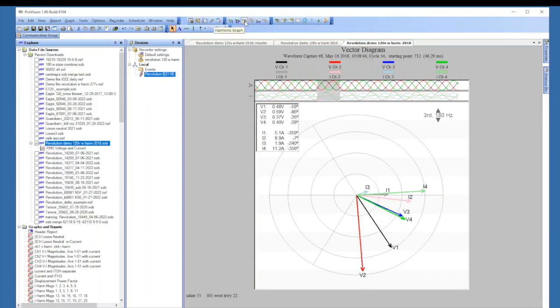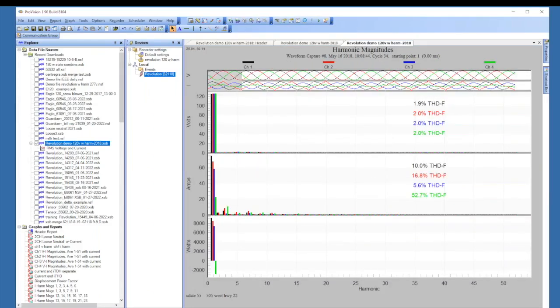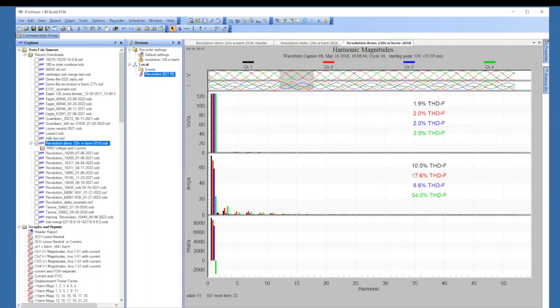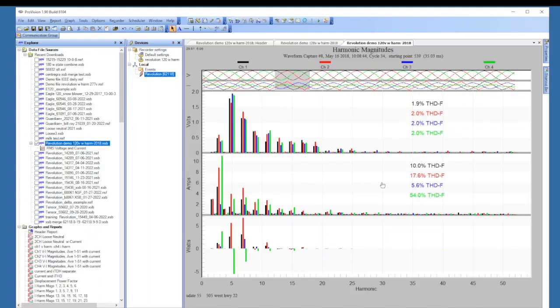If we go and click on the H for the harmonic, we get harmonics, and we can see that we have total harmonic distortion there. So again, we're looking at just a small sampling, but harmonics should be repeatable. So the THD will give you an idea of what your total harmonic distortion is. Even if you didn't record THD or didn't record harmonics, you can right click and do show fundamental. And you can page down and page up through these too.